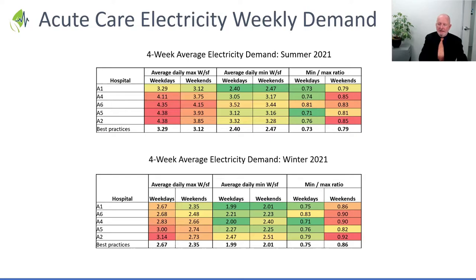On weekdays, A1 is around 3.3 watts per square foot. It drops down to 2.4 at night, so that's around three-quarters—it drops its load by about a quarter. Heads up for everybody interested: one of our key areas of research next year is to look really hard at that 2.4 watts per square foot valley number and look at the component parts—as well as they're doing with scheduling, are there still things running at night that can make that valley even deeper? But if you look across all of those right now, the best practice row there are the numbers I'd like you to write down. Again, you'll have them in a few weeks in the final report.